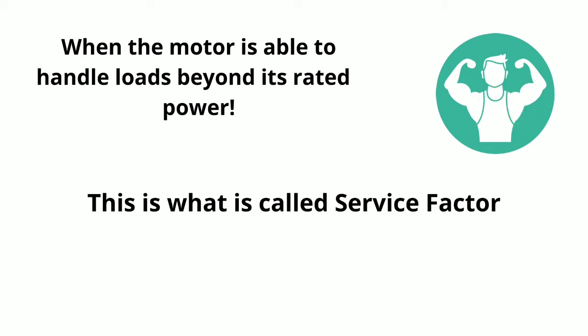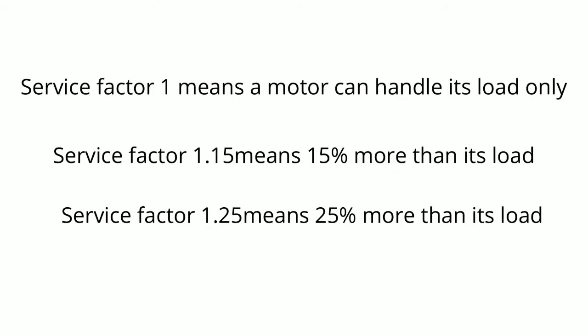A motor with service factor of 1 means that it only can handle its rated power. While a motor of service factor of 1.25 can handle 25% beyond its rated load.